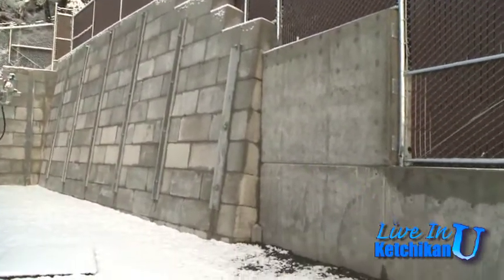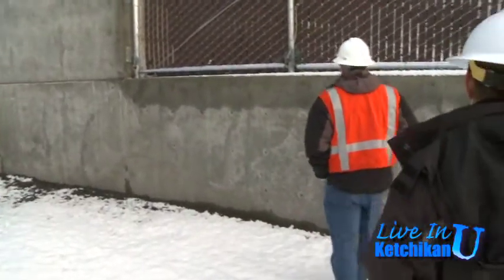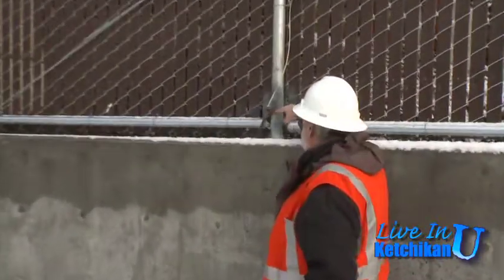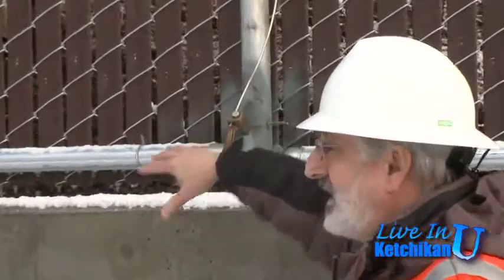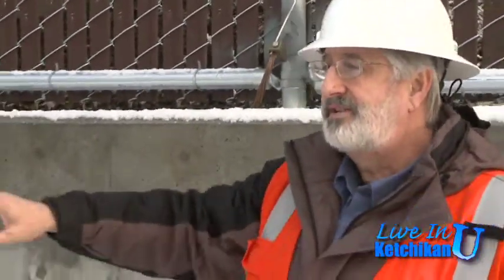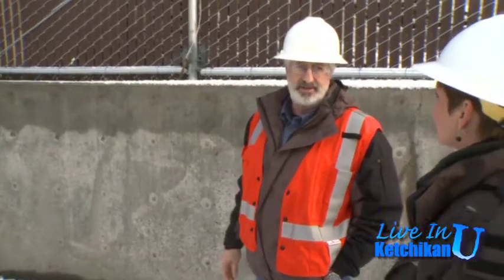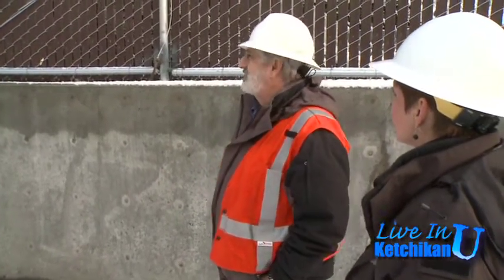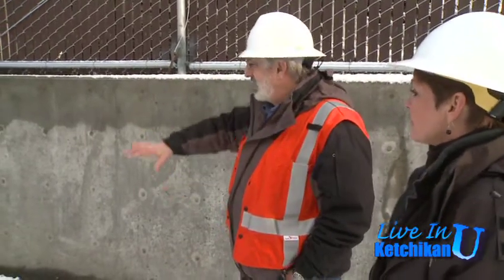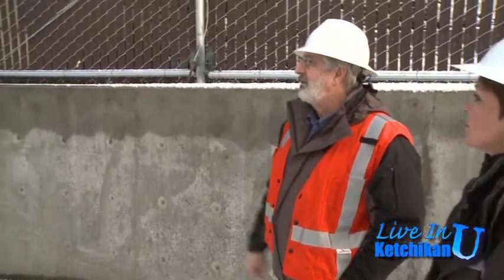So let's talk a little bit about grounding. If you notice, all the fence posts are grounded. This whole area has a very extensive ground grid, probably the best grounded substation we have in our system. We made an extra effort to make sure the ground grid was very extensive, and it goes down below us maybe 3 or 4 feet. All the devices are very adequately grounded.